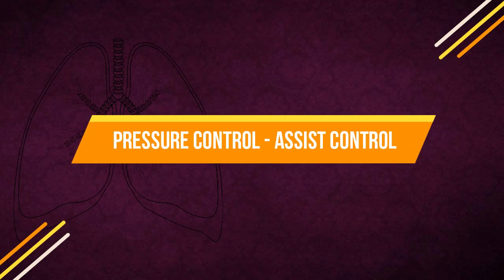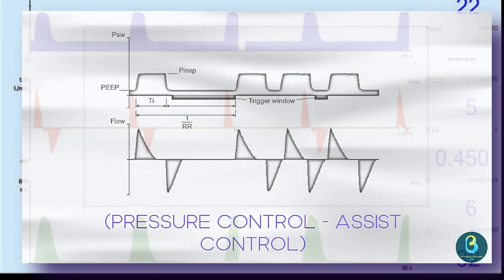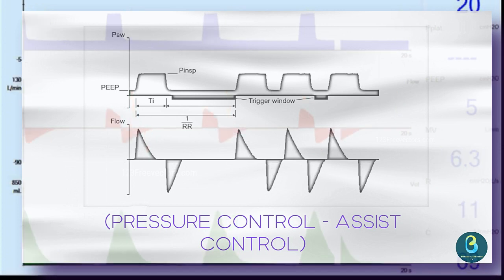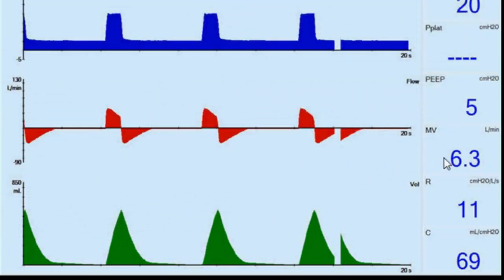Another mode is Pressure Control Assist Control. Every detected breathing attempt at PEEP level triggers a mandatory breath, so the patient determines the number of additional mandatory breaths. To give the patient sufficient time for expiration, it is not possible to trigger another mandatory breath immediately after a completed breath. If no mandatory breath has been triggered after the expiratory time completes, a mandatory breath is automatically applied at backup frequency, so the respiratory rate adjuster defines the minimum ventilation frequency.